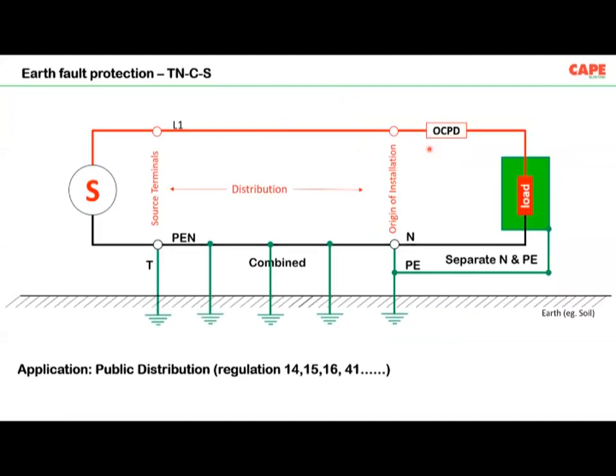Also, in the previous slide, I showed the fault loop impedance, and how earth fault protection is achieved in the case of a TN-C-S system. TN-C-S is a system earthing generally used for public electricity distribution. In that case, imagine there is a fault here. The fault current returns to the source through the PEN conductor. It comes back to the fault through the live conductor. The impedance of this loop decides the amount of fault current, and the amount of fault current decides the disconnection time of the protective device, such as an MCB. Remember, for earth fault protection, an RCD is an additional protection. It is not the primary protection. The primary protection is your fuse or MCB. So the earth fault loop impedance of this circuit must be low enough so that a higher current flows and disconnects the MCB, and the calculations are given in the standard.